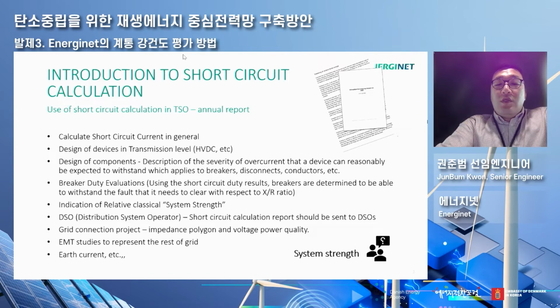I'll give you an example. When we try to interconnect with a vendor or developer, we need to tell them the stage our grid or power system is at, when it is weakest, and when it is strongest. We need to inform them, and when we try to design, we need to describe the severity of overcurrent that a device can reasonably be expected to withstand, which applies to breakers, disconnects, and conductors.